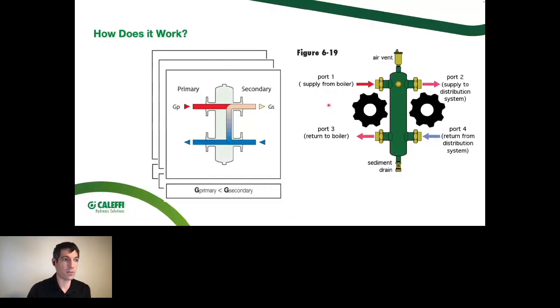The opposite could be true. So let's say this is even kind of a tricky example. Let's say we have a 400,000 BTU per hour boiler, and we have a 400,000 BTU per hour load. Everything is sized great, right on the numbers. Both are the exact same number. There is a scenario where the boiler is turning away at 100%, all of the zones are wide open, and the circulator is moving at the maximum speed that we had planned for. It's a design day. We could still have these wheels spinning at different speeds.